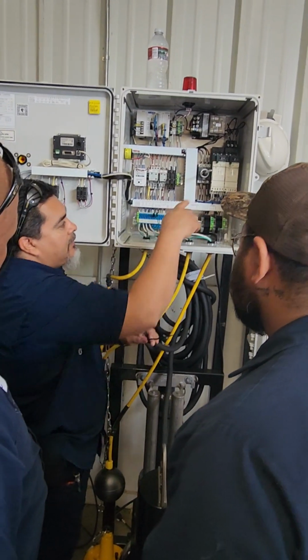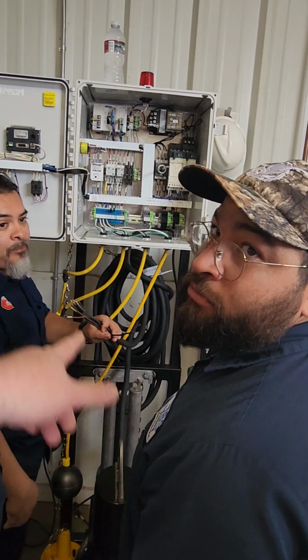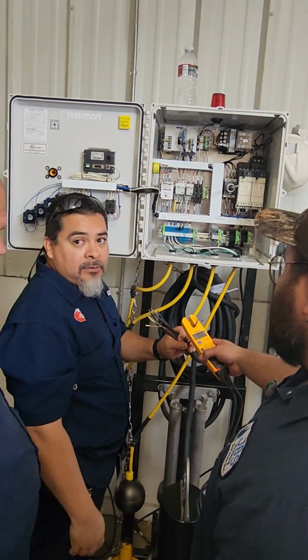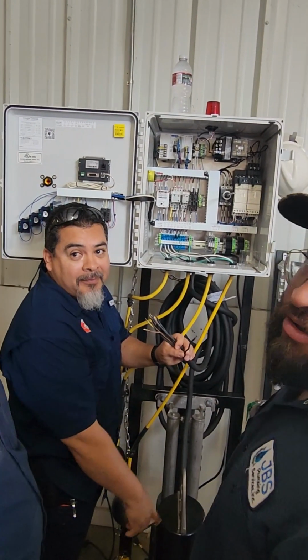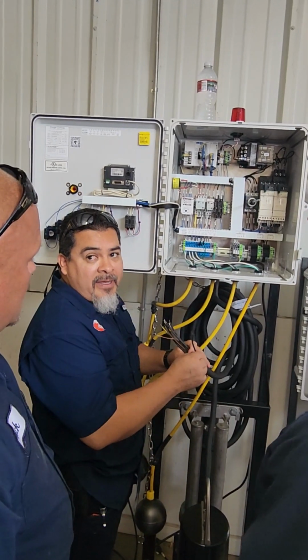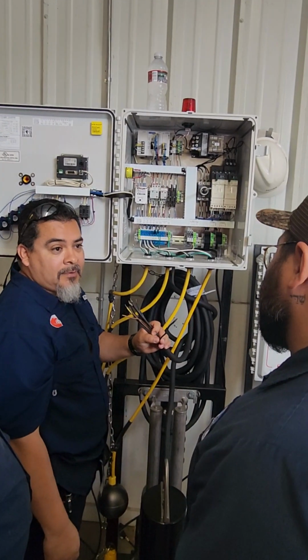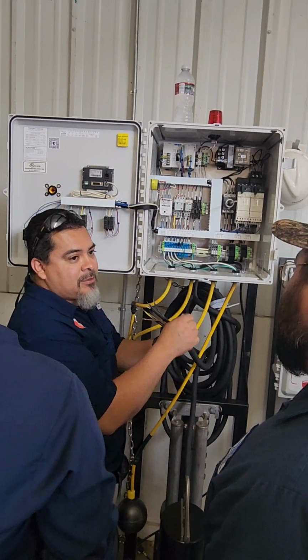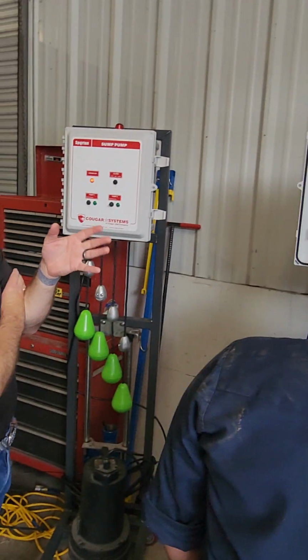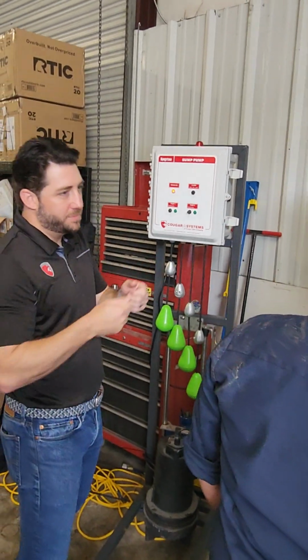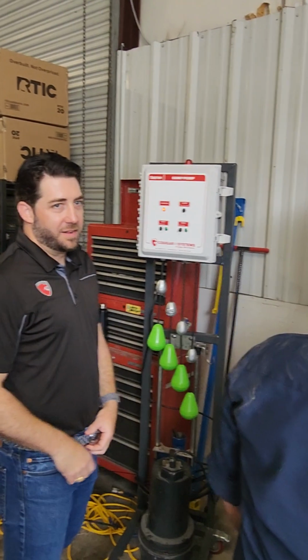High amperage. So when it keeps tripping, what would you get when you put it on there? Not on, because the pump has to be running. You have to run the pump while you're doing it, meaning the whole panel is hot when y'all are doing that. So be careful. This is how you're working in the hot panel.